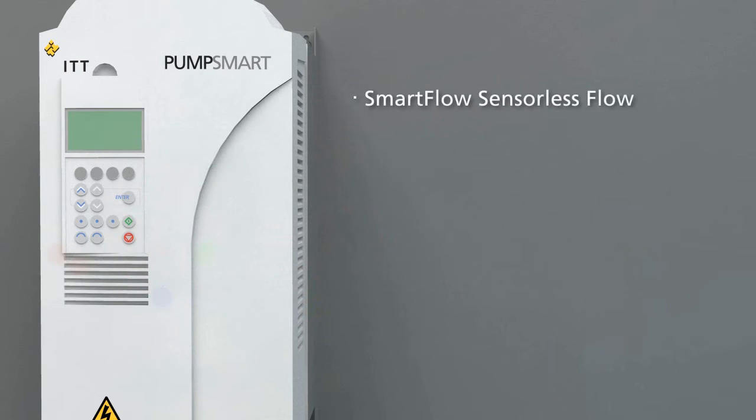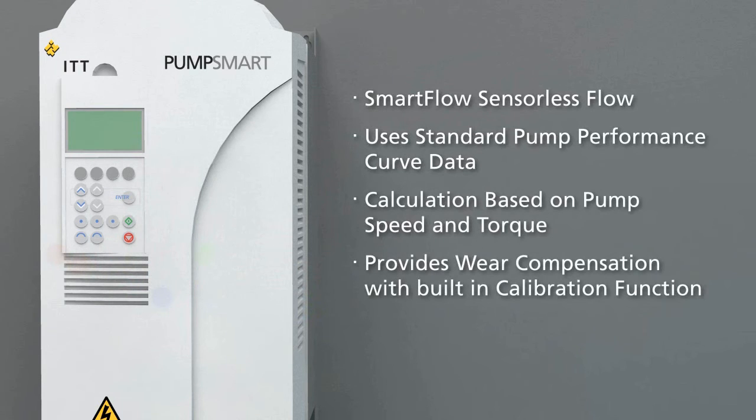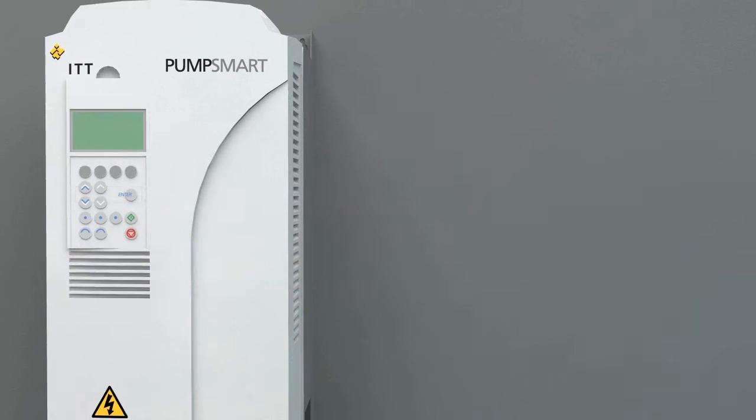SmartFlow manages flow without sensors. It uses standard pump performance curve data, provides calculations based on pump speed and torque, provides wear compensation with a built-in calibration function, and is accurate to within plus or minus 5% of pump rated flow.